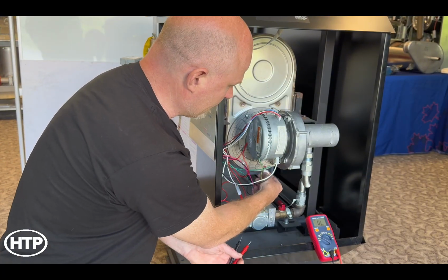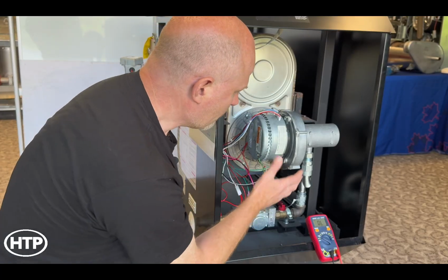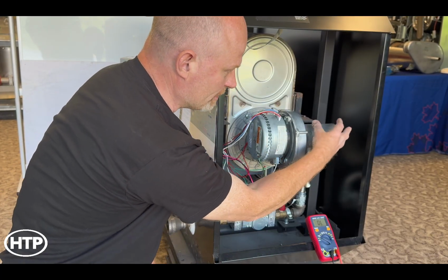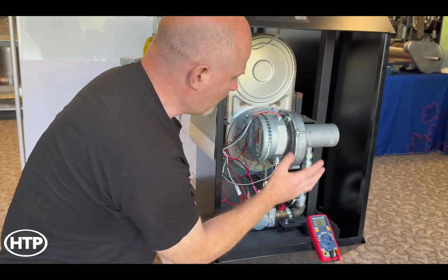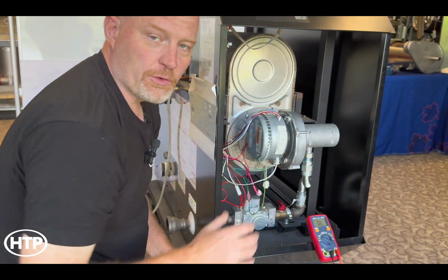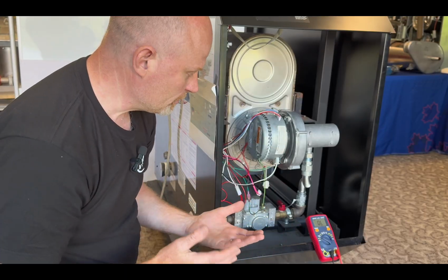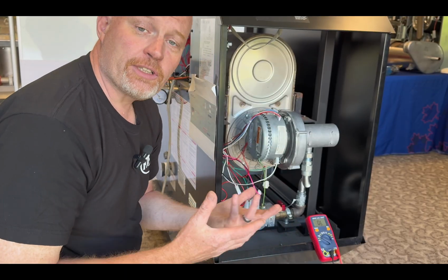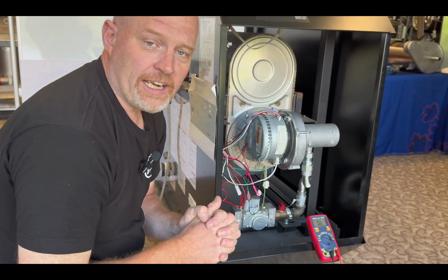Once you've verified that that is either working or not, if you find it's not working, sometimes debris and residue will get sucked in through here. It can make the flapper a little bit sticky. Basically, you're going to want to remove the fan, remove the flapper, wash the componentry, make sure it's actuating freely and there's no stiffness. If you still can't get it working reliably, unfortunately, at that point, you're going to have to replace it. But hopefully that helps you diagnose the problem.